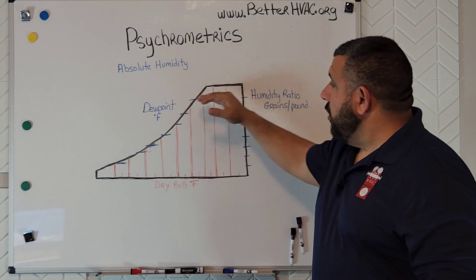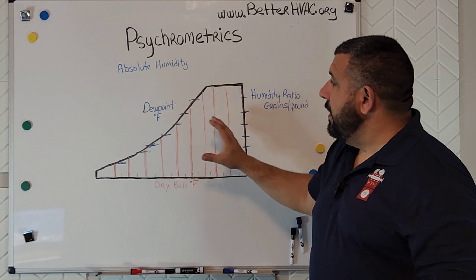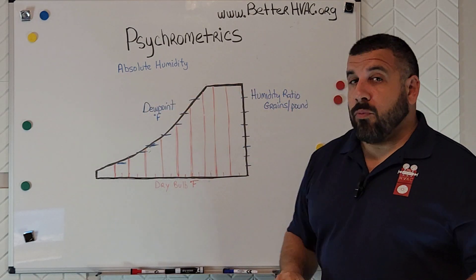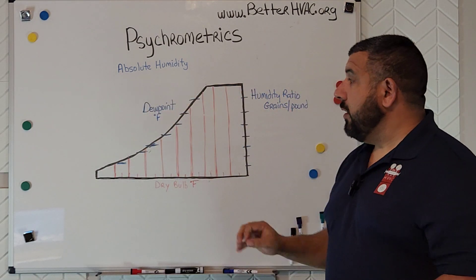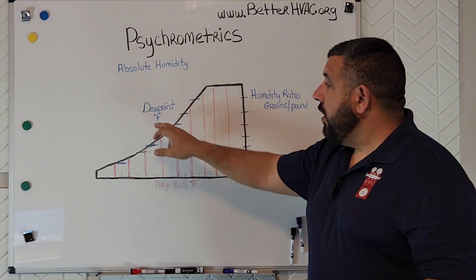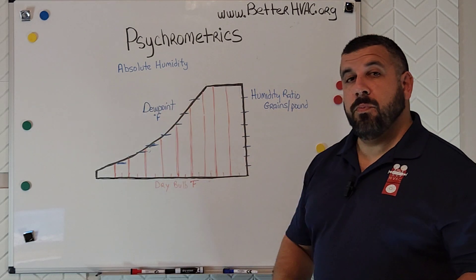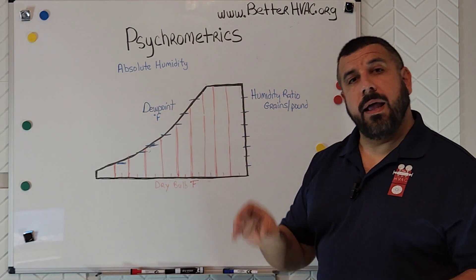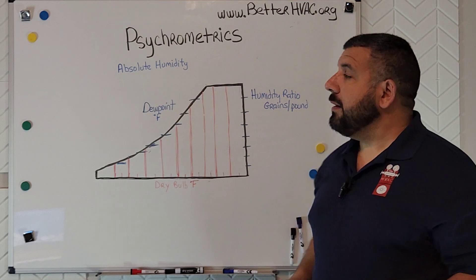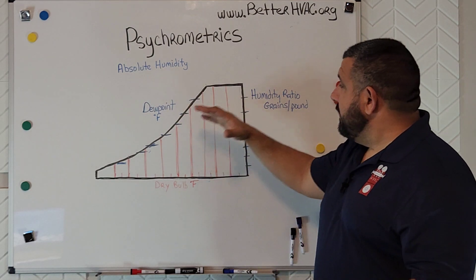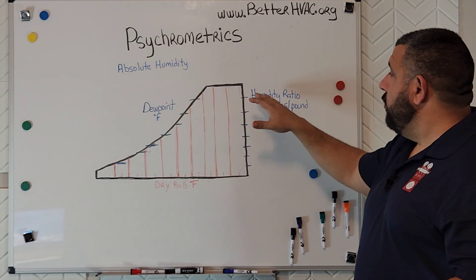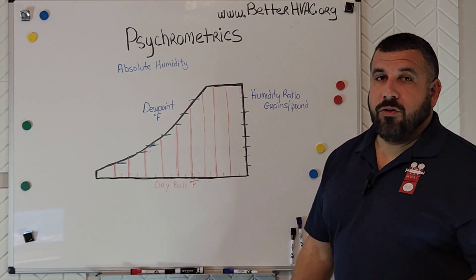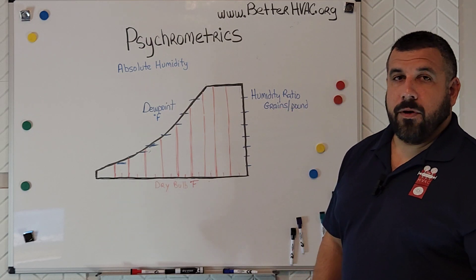With this chart, you can read absolute humidity on the left side of the chart, and you can also read it on the right side. On the left side, we read it in the form of dew point, and that unit of measurement is degrees Fahrenheit. We're going to come back to dew point. On the right side of the chart, we have what we call humidity ratio, and that's measured in grains per pound.